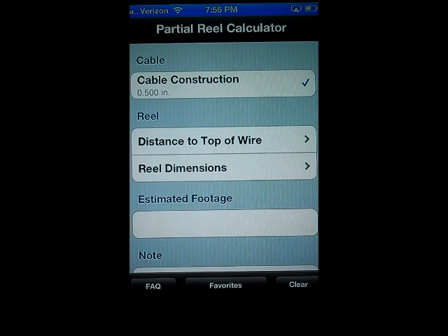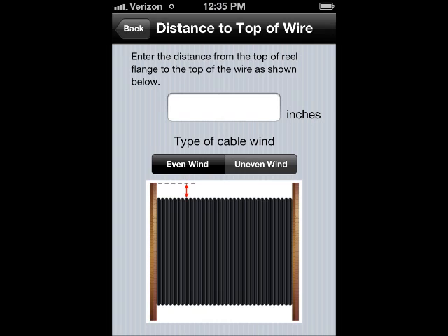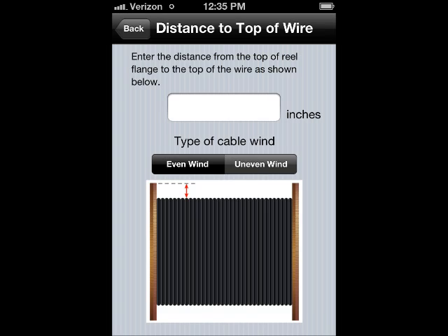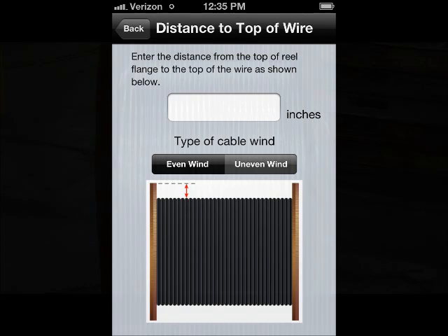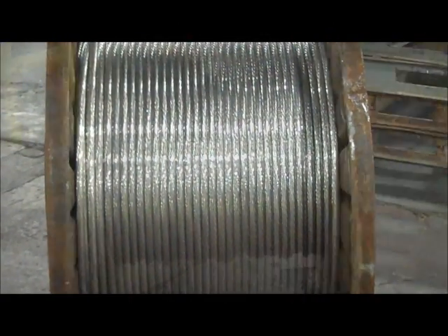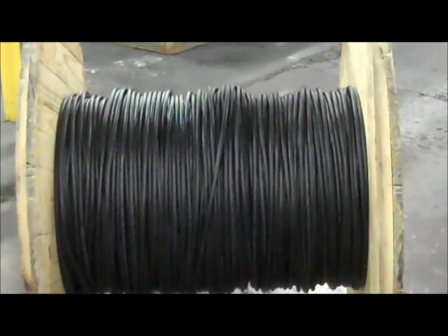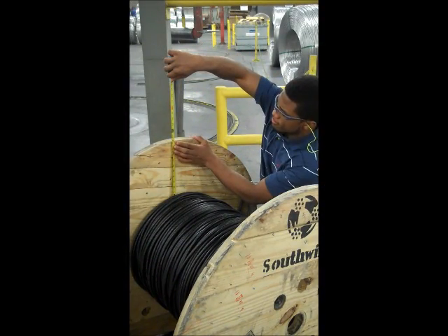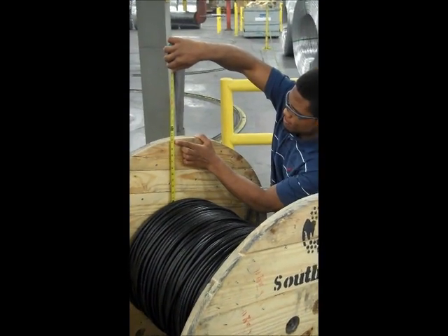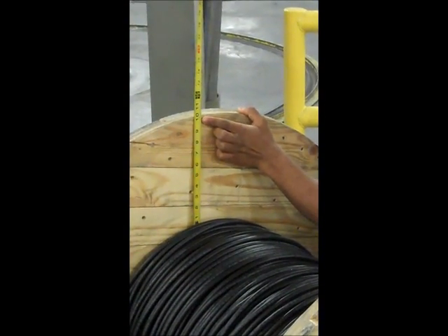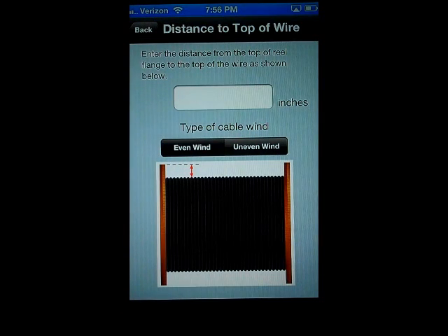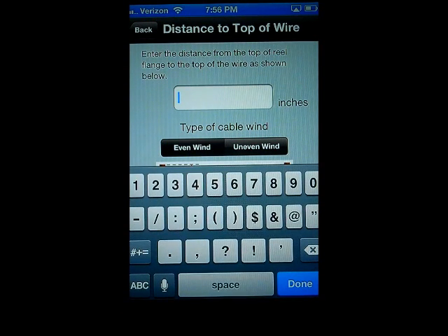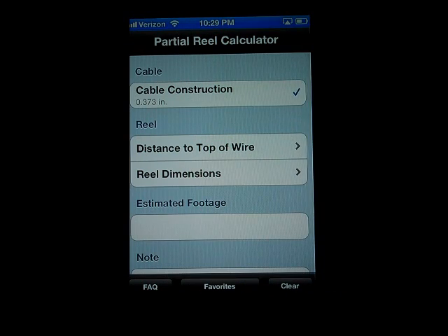Next, you will enter the reel information. Start with the distance to the top of the wire. First, specify the wind type. The wind type will depend on the reel you are using. This reel is an even wind, so we would select that option. Now take the measurement. Use the side of the flange and measure on the side with the least amount of wire. Measure from the tip of the flange to the top of the wire. Enter the value and press Done. Please note this value will vary with each individual reel and must always be measured manually.